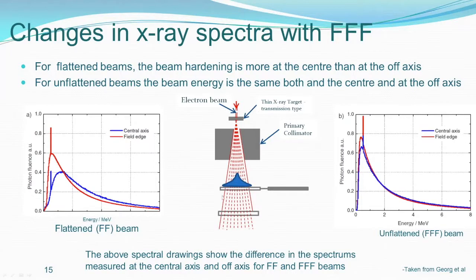So even though you say the flattening filter brings in a uniform intensity, it is not actually bringing in a uniform energy fluence across the beam. The energy fluence across the beam will change because of this. You can see this graph. This is the central axis.